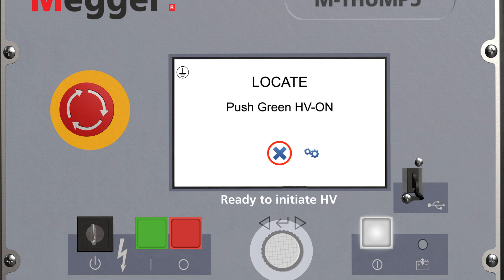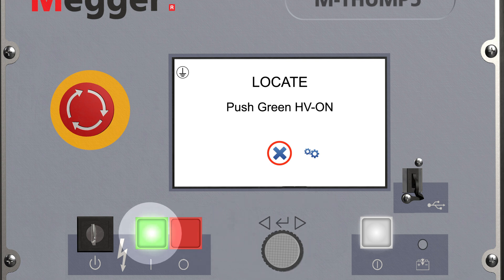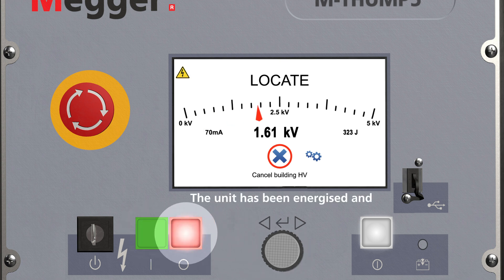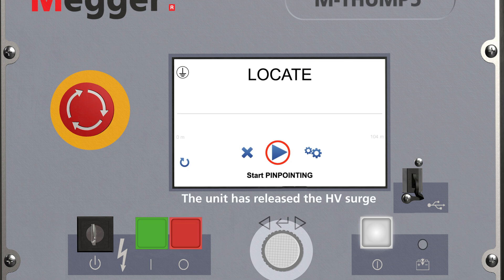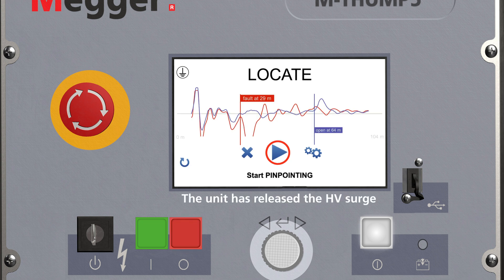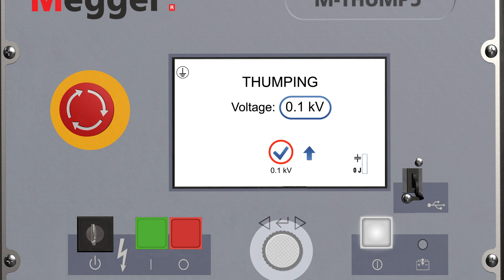Select the voltage set point for the arc pre-location. Ready for measurement. Confirm the high voltage initiation with the green button. You can abort the building of high voltage with the red button or the rotary knob. The unit has been energized and is building high voltage. The unit released the HV surge and the flashover at the fault was captured. In the graphic, you can see the distance to the cable fault. Now the pinpointing begins.